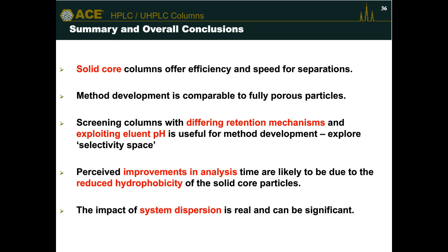Lots of the speed improvements are based on the reduced hydrophobicity of these particles. And do be aware that your instrument plays a big role as well. So making sure you've got fresh connections, you've got good fittings, you've got narrow bore tubing, all of that will help to give much better chromatography.